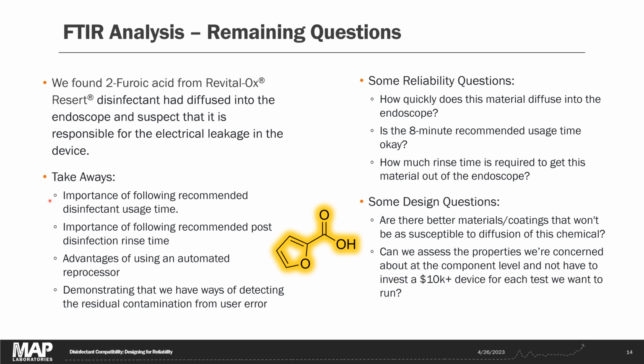Key takeaways at this point are that it's important to follow the recommended disinfectant usage time. If you exceed that time, you're increasing the likelihood that material is going to diffuse into the endoscope and cause problems. Equally important is to follow the manufacturer recommendations for rinsing the endoscope after disinfection. If they say rinse for 5 minutes or 10 minutes, you have to do that because that rinse is important for extracting any chemicals that have diffused into the endoscope.